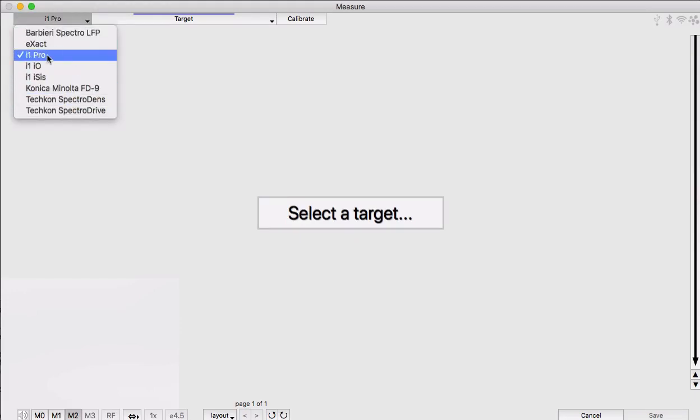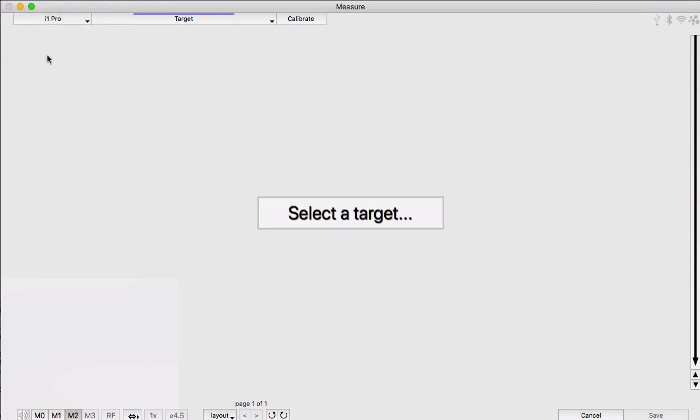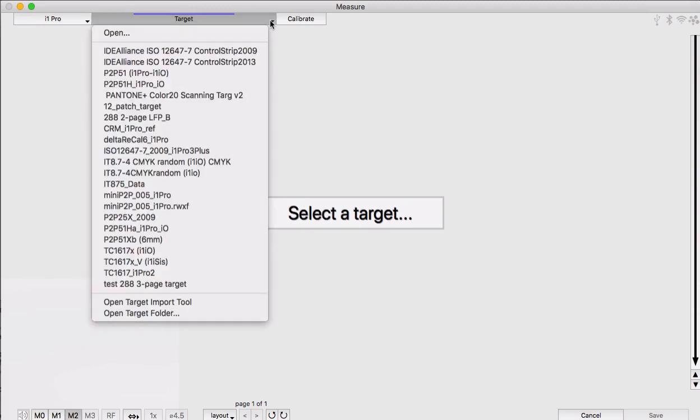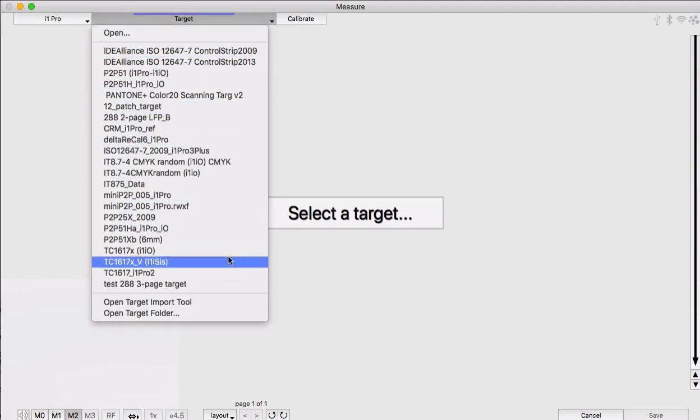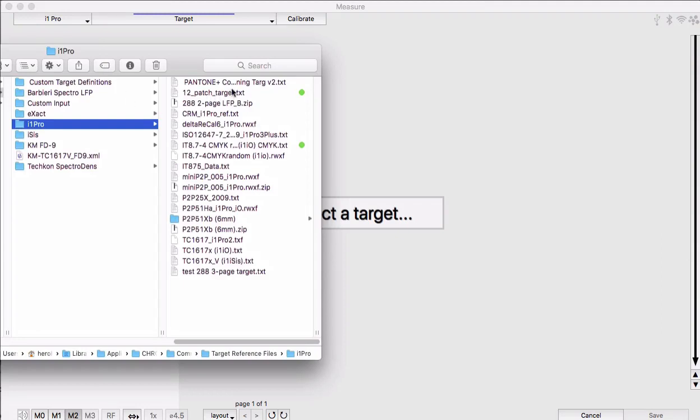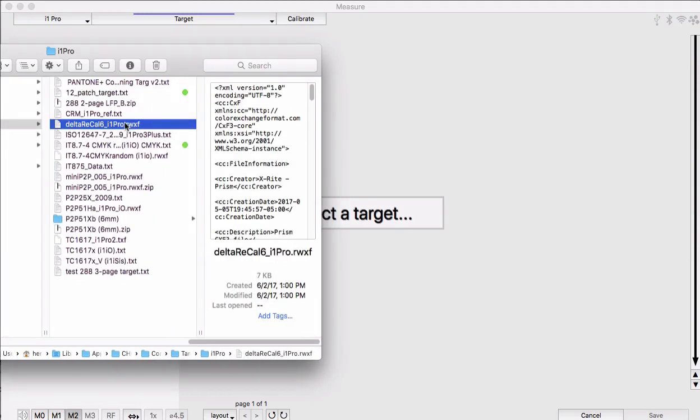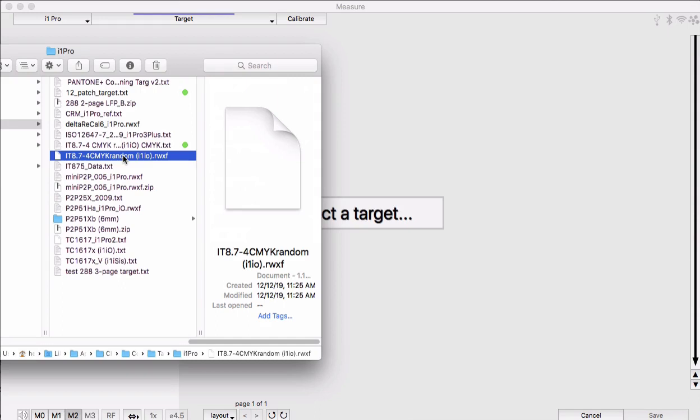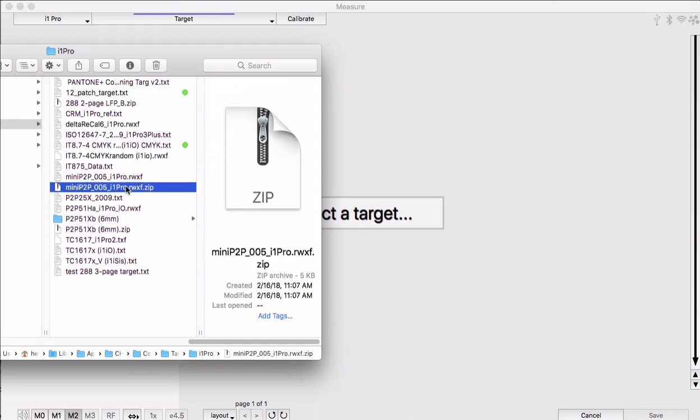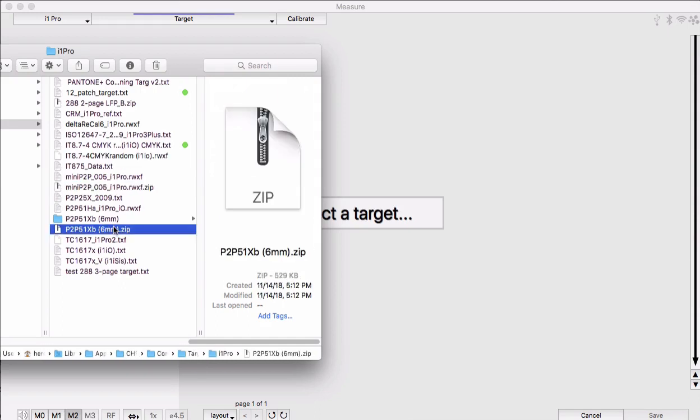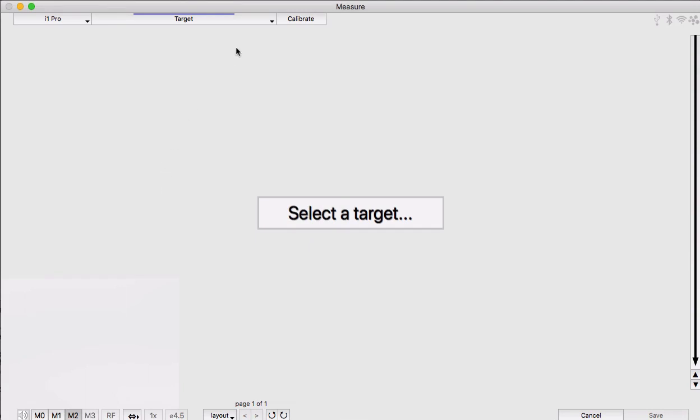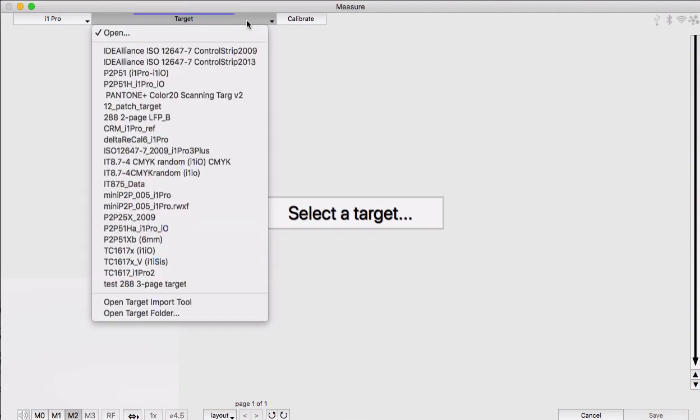I always like to point out to people that our measurement tool can use target references from different manufacturers, even companies different from the instrument that you're using. These RWXF files are from X-Rite for the ISIS or i1 Pro. And then Barbieri puts out a zip file as a reference for an LFP or something, the CGATS text file. But you can use any of those to measure using the i1 Pro 3.